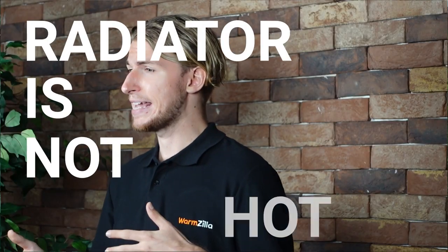So what do you do if your radiator is not getting hot at all? If your heating is on and other radiators are working fine, you may have stuck or frozen valves. These stop water from getting into the radiator, or again sludge or rust may be to blame. In some cases there may be a bigger problem going back to your boiler. We recommend you ask a gas safe registered engineer to take a look. You might need to have your central heating system power flushed.